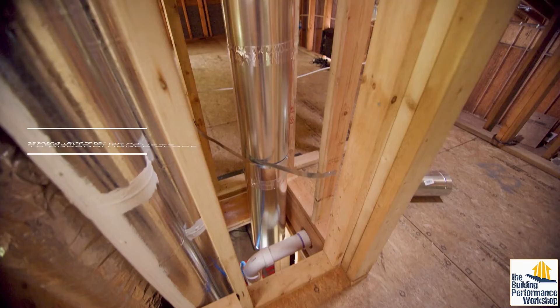Pause for one second. Absolutely. A lot of my clients are doing encapsulated conditioned attics, and I actually have zero duct load on probably about 75% of the loads that I run, but it still shows up, which is why the mechanism is there. So it's still there when you... Yeah, the math is in there, they built it in so that, because you needed to make a guess, it would still work.